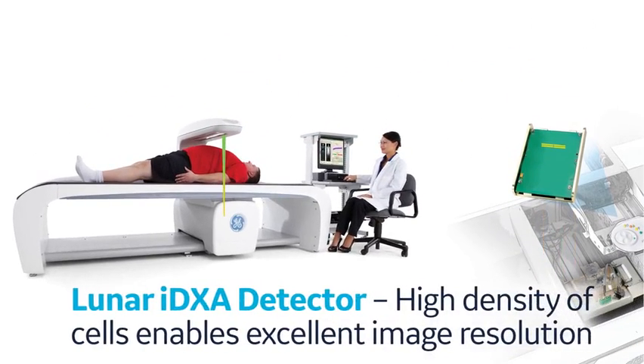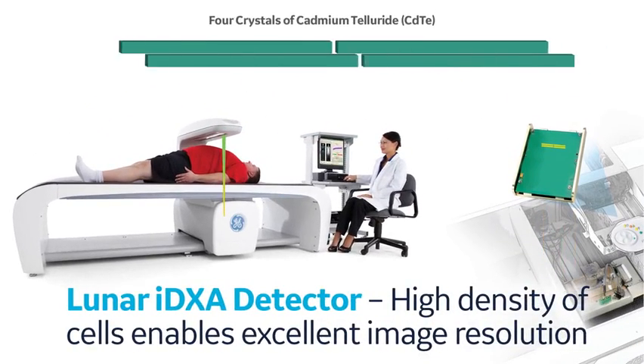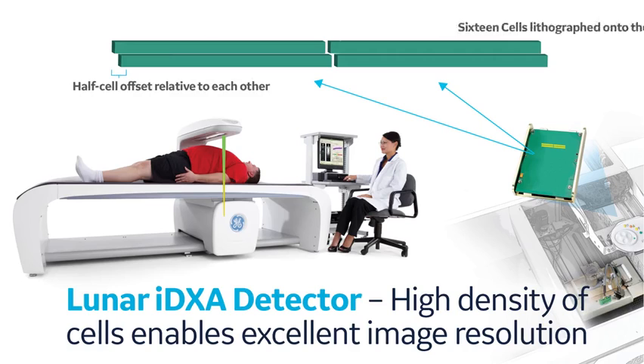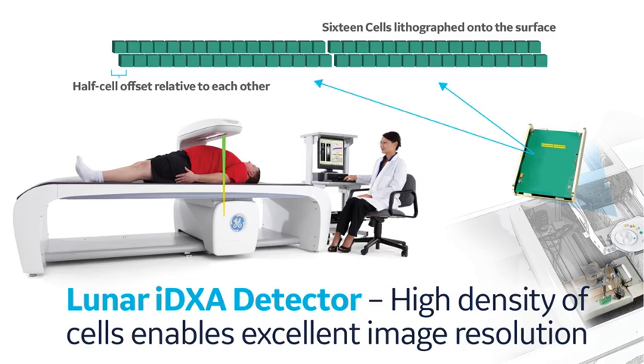A Lunar iDXA detector consists of a patented array structure of four cadmium telluride crystals. Each crystal row is arranged with a half-cell offset relative to each other. On each crystal, there are 16 cells lithographed onto the surface.